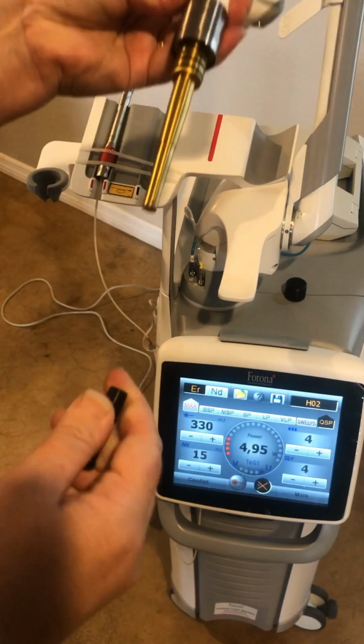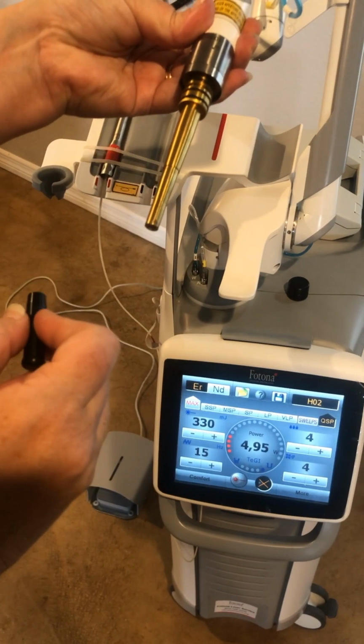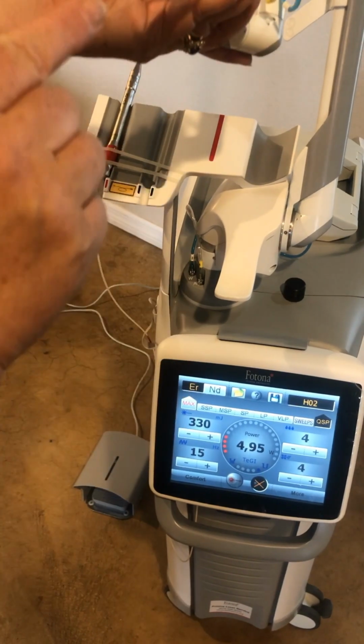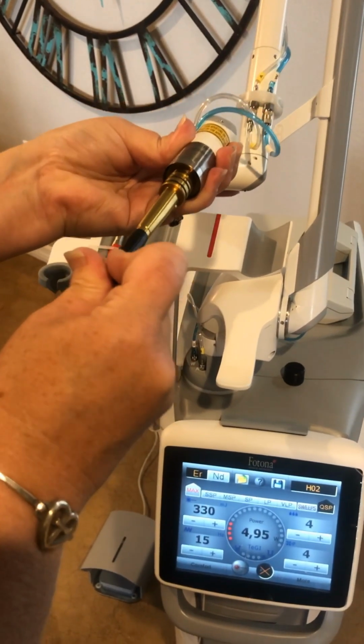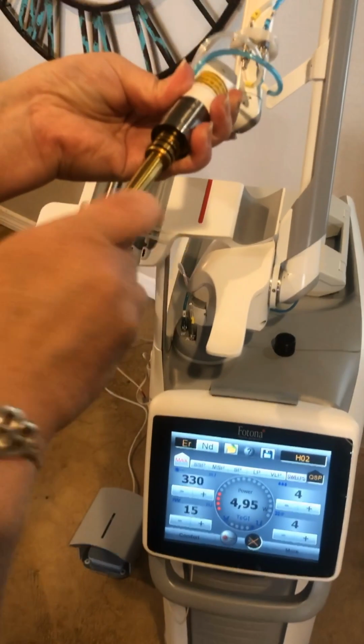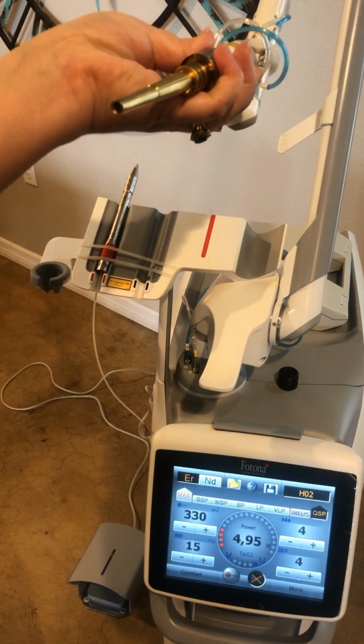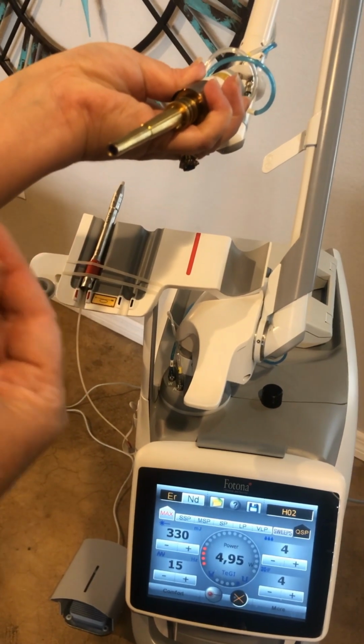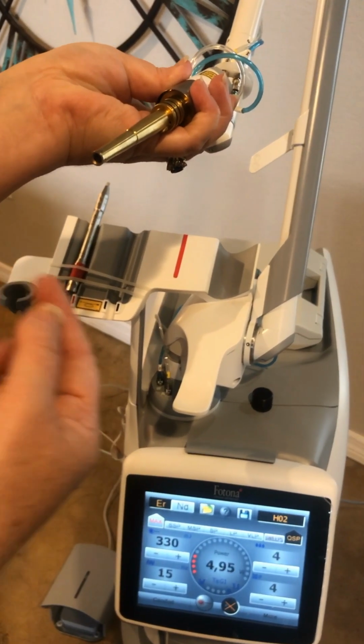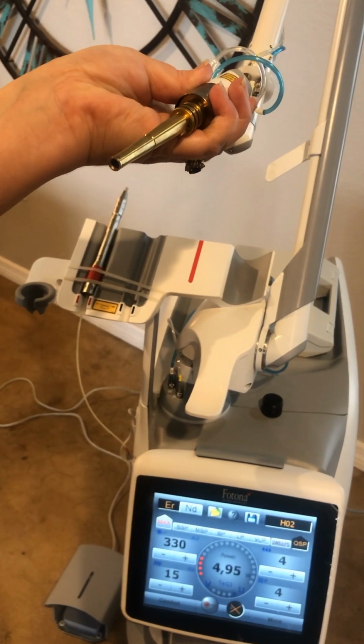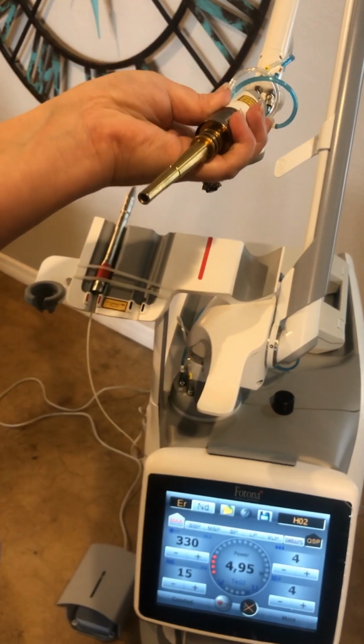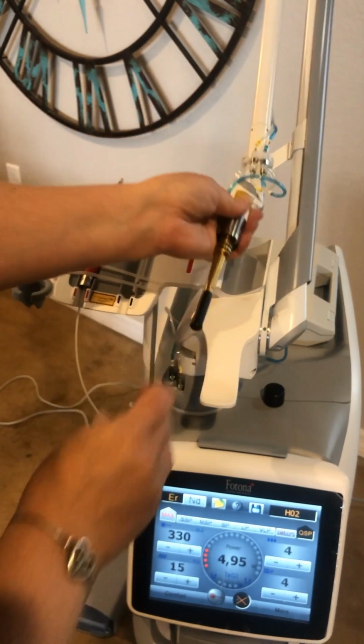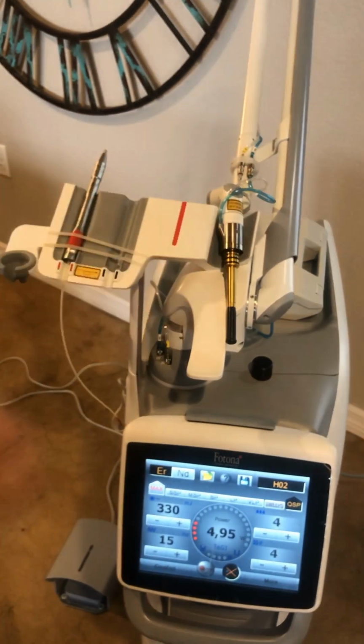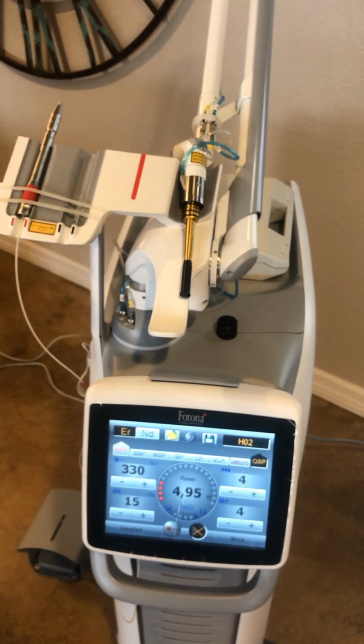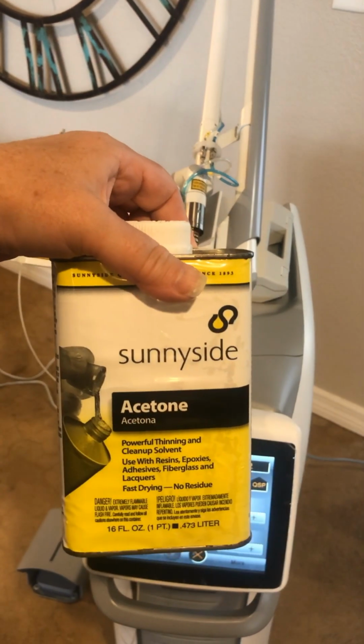Okay. So this is the HC coupler. This piece is used whenever you have the other parts of the handpiece in sterilization; the end lens should be covered to protect it. This lens is also important to check and make sure that you don't have any fingerprint marks on it. If there's fingerprints, the human oils have water molecules in them, and it will react with the erbium energy. So you want to make sure that that's clear. How you clean that is with a Q-tip, and always either 70% alcohol, or better yet, 100% acetone.